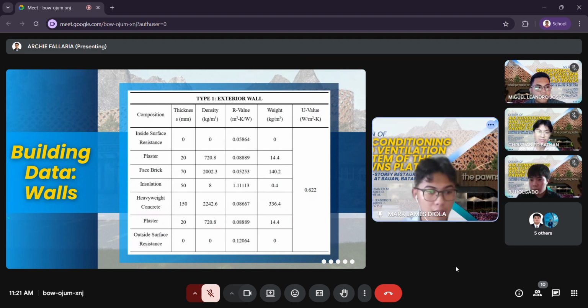Next, for the building data, the walls are classified into two types, each having a distinct purpose in the building's climate control and ventilation strategy. First is the type 1 walls, which are the exterior walls, while the type 2 walls are the partition walls. The exterior wall is made of plaster, face brick, insulation, and heavy weight concrete. This material is 310 millimeters thick and has an overall U value of 0.622 watt per meter squared Kelvin.